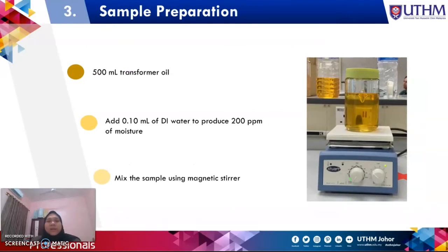So we're going to move to the sample preparation. Basically, we use 500 milliliters of transformer oil, and then we add 0.1 milliliter of deionized water into the 500 milliliters of transformer oil to produce 200 ppm of moisture content. This is the glass container that we use to put the transformer oil and the deionized water, and then we use this magnetic stirrer to mix our sample.